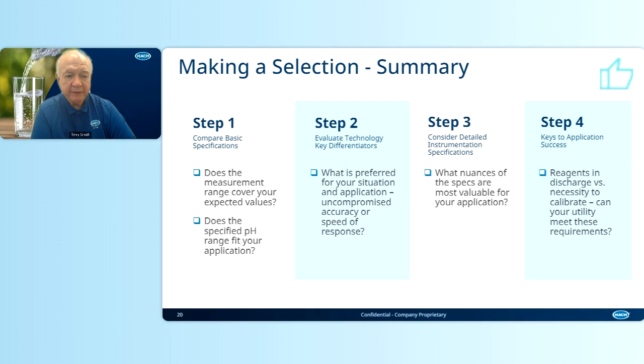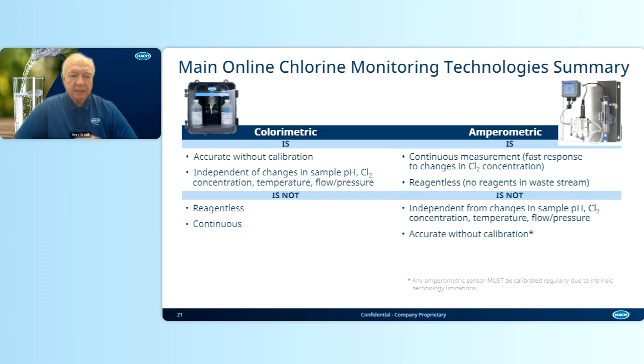So we go through and we compare the basic specifications. We evaluate technology key differentiators, consider detailed instrument specifications, and keys to successful application. The whole idea, we go through this summary. Here's what we look at. Colorimetric is accurate without calibration, independent of changes in sample pH, chlorine concentration, temperature, flow, and pressure. It is not reagentless, and it is not continuous.